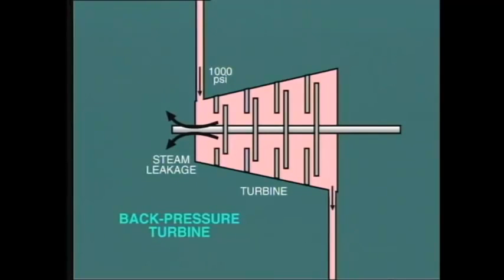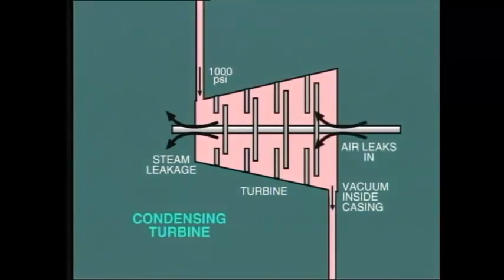And would we not have the same condition at the low pressure end? Well, yes, if this is a back pressure turbine with a positive exhaust pressure at, say, 50 psi or over. Although the pressure and temperature is less, there would still be leakage between the casing and the rotating shaft. But what about the case of a condensing turbine? Well, in this situation, there is a vacuum inside the casing at the low pressure end. So instead of steam leaking out, air would leak in, and we do not like that either. It could lead to a loss of vacuum and consequent loss of efficiency.